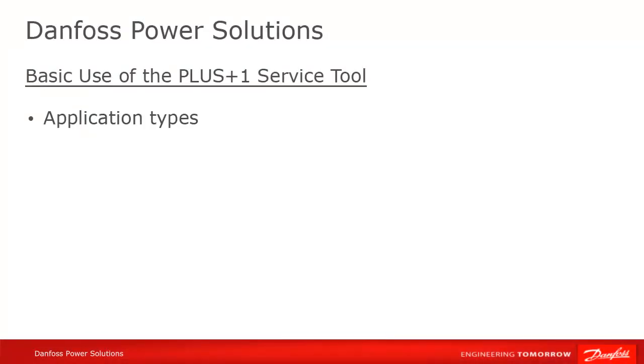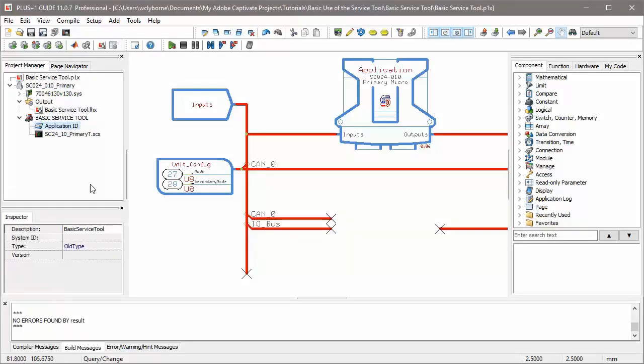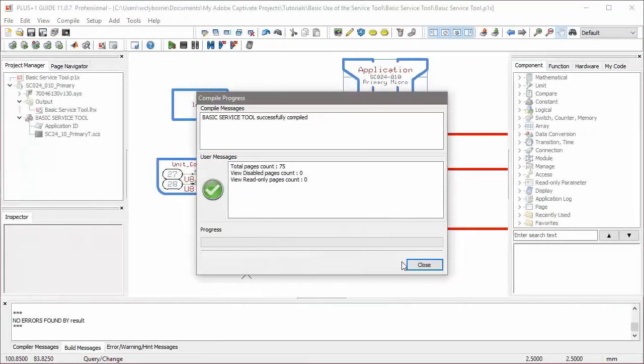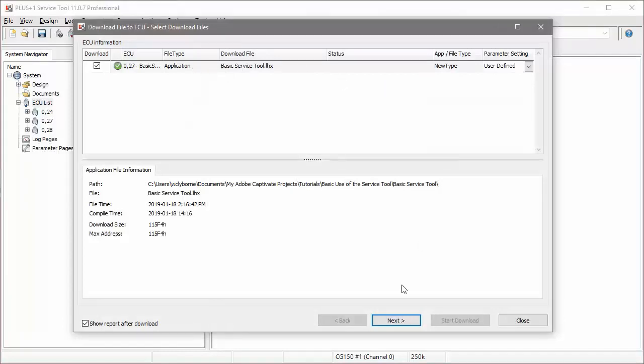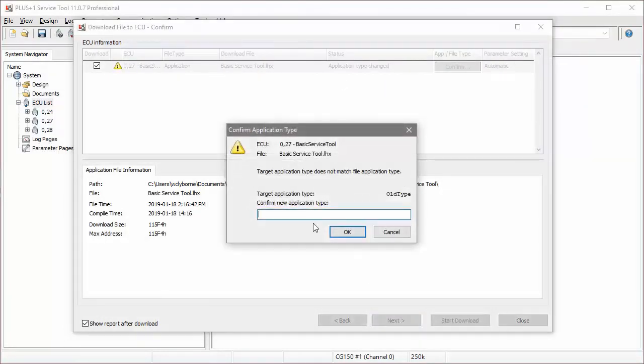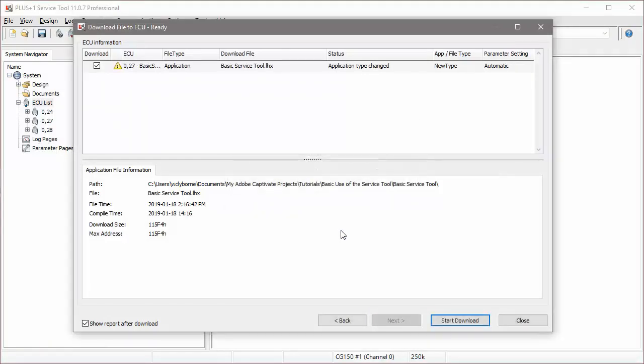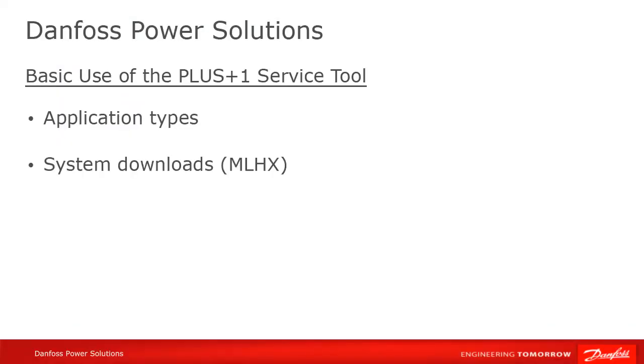If you have multiple valid candidates for download and you want to minimize the chance of mixing up the device and the application, you can do this by using application types in your program. If the application type of the new program is different from that which is currently on the controller, the service tool will force you to confirm the download before proceeding. Another way to ensure that a specific application is downloaded to a specific controller is to use system downloads or MLHX files. Search the videos or use our user manual for more information on application types and system downloads.